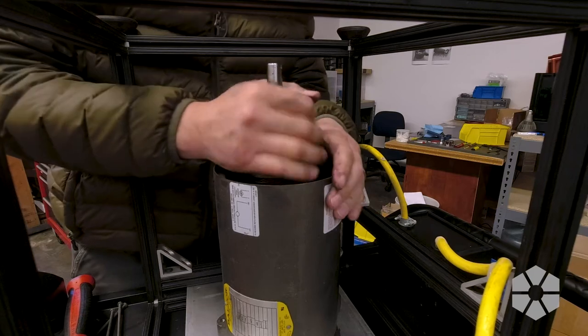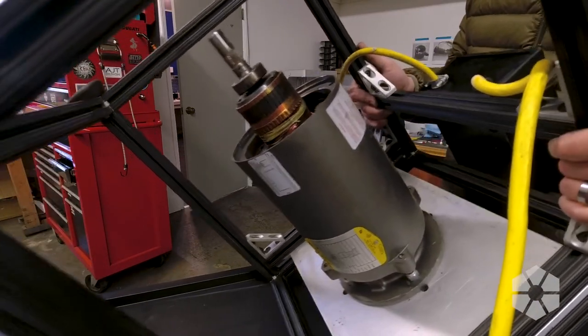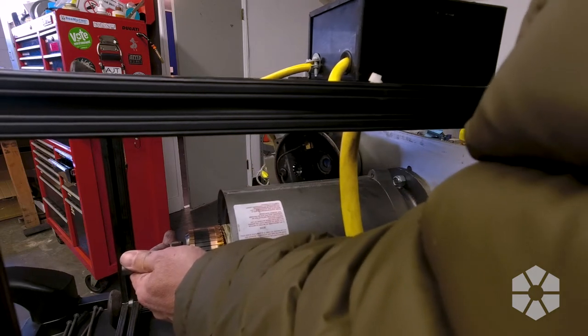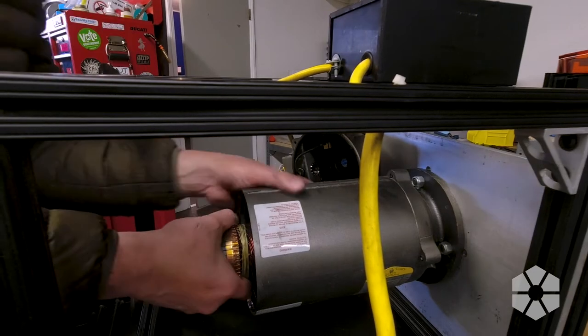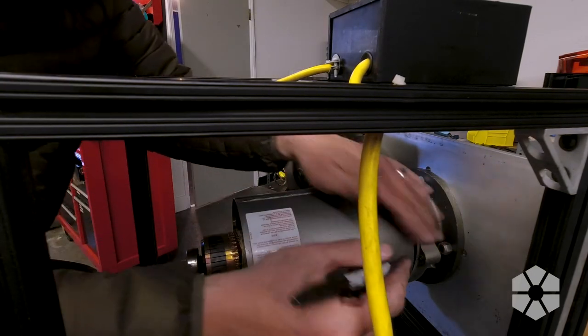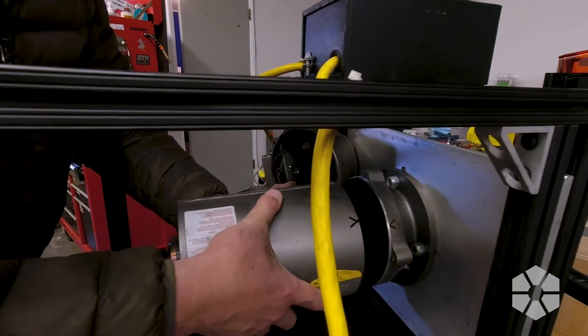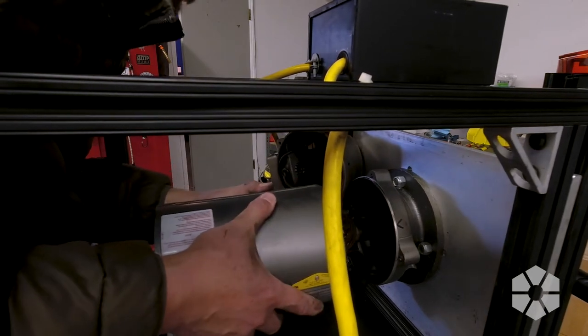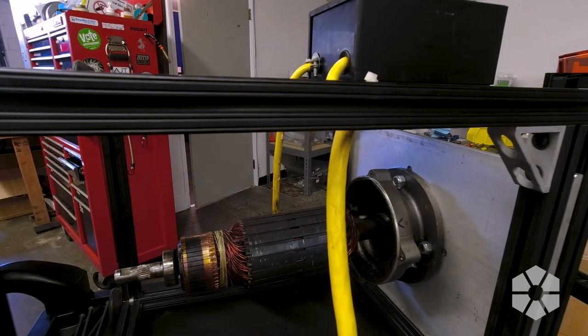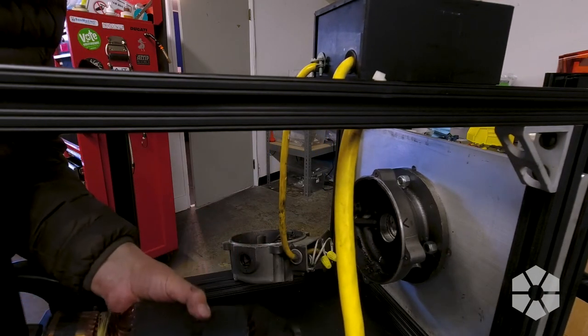To injure myself further or not, that is the question. Should we try tipping it? That will pull this forward. Whoa! This end case came in, which I wasn't anticipating. So before this goes too far, we're just gonna make a witness mark here in case this orientation is important. Holy cow — this is just being held by the magnetic field of the windings. Okay, little fella — we're out. It's definitely time for more vacuuming.